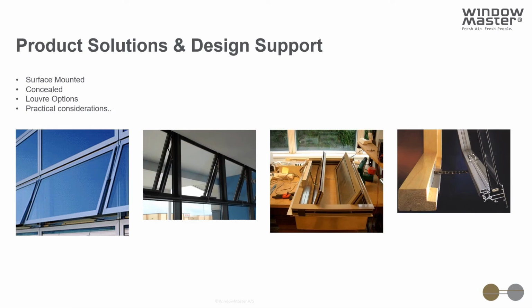WindowMaster can give input on a number of different design and product solutions. In terms of the number of actuators required on vents, typically on aluminium windows, for example, you might need more than one actuator where vents are over 1200 millimeters wide. This isn't necessarily about the force the actuator can exhibit, it's more about the capacity to achieve a seal on the window when pulling it closed against the seal at only one point in the center. Wider windows will flex a small amount depending on the profile used, and we can help offer guidance on that, as well as other practicalities like concealing actuators and the risks around that, wiring routes, and other methods to make the installation as neat as possible while delivering a high level of performance, being really quiet, and delivering effective control.